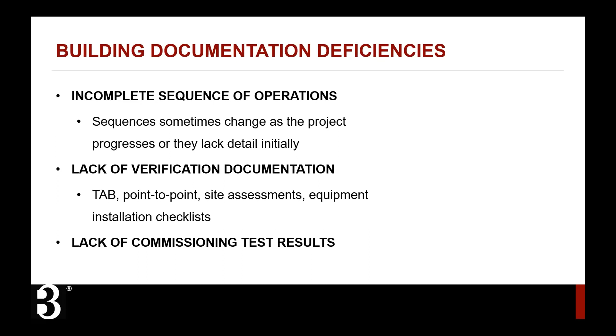The next issue is lack of commissioning test results in general, referring to functional performance tests. During testing you can fail a sequence, such as a damper not operating as intended. But if that failure is never noted in the issue log during construction and never fixed, the owner is missing results. They may see it failed but not know if it was corrected, or whether action was taken by the commissioning agent to ensure the owner's requirements from the owner project requirements were ultimately met.